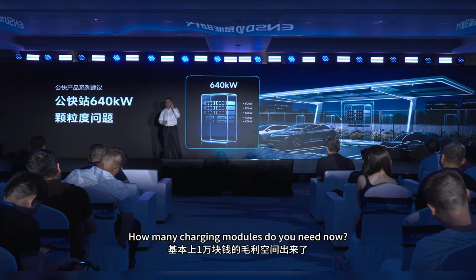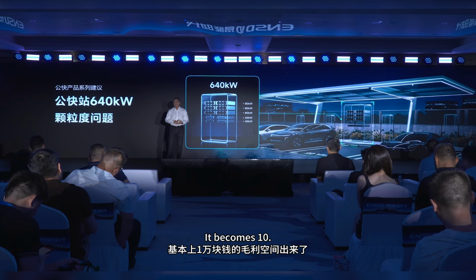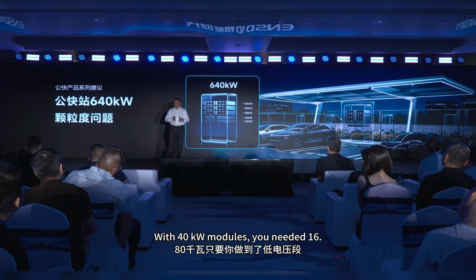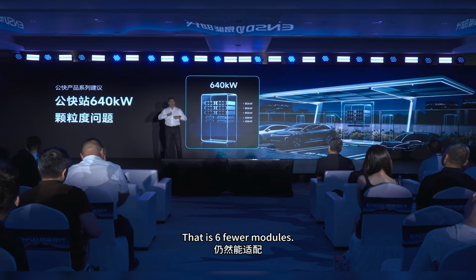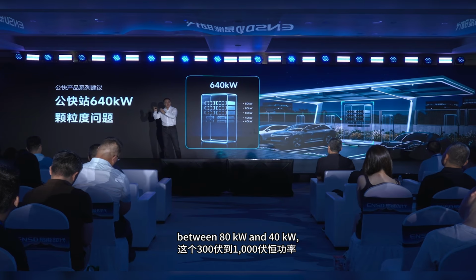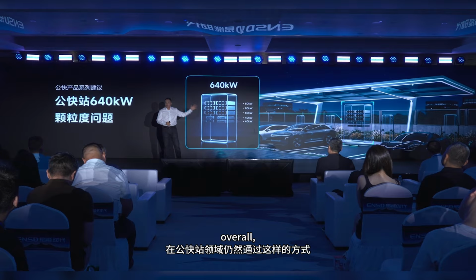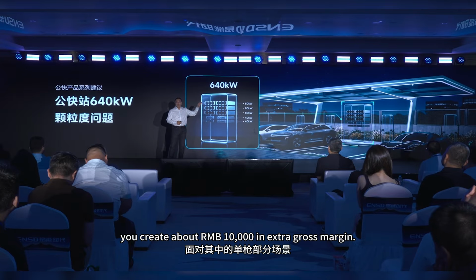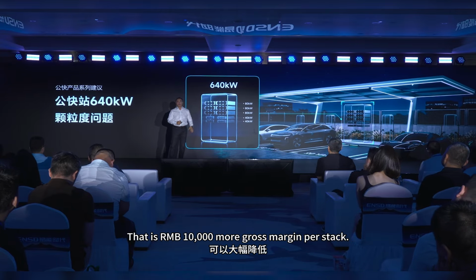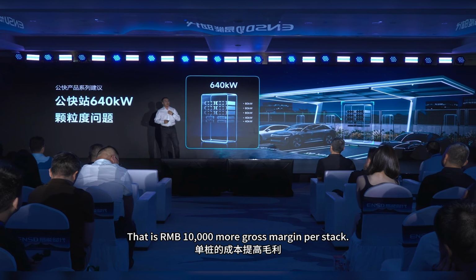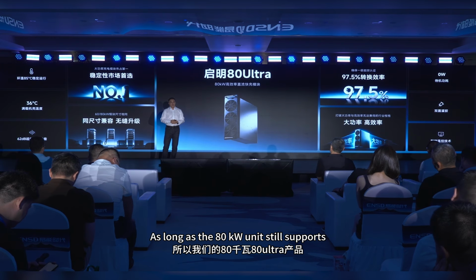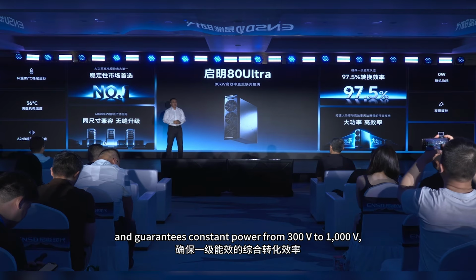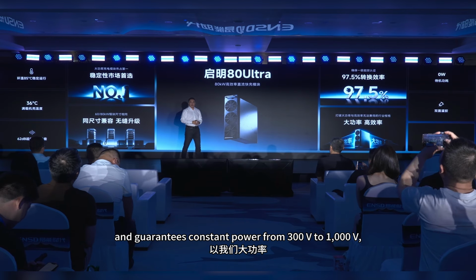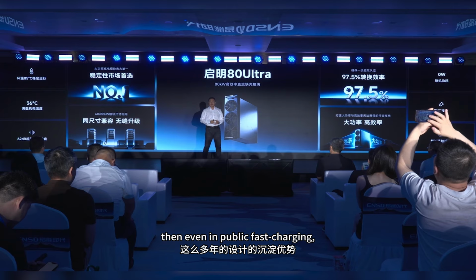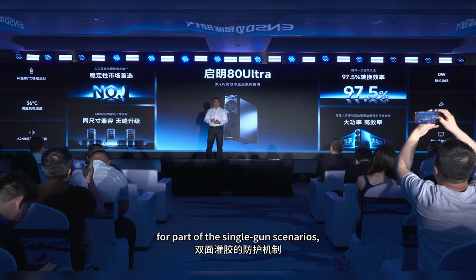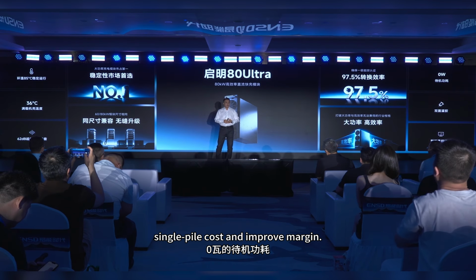But think about it. How many charging modules do you need now? It becomes 10. With 40 kilowatts modules, you needed 16. That is 6 fewer modules, even after considering the cost per watt gap between 80 kilowatts and 40 kilowatts. Overall, you create about RMB 10,000 more gross margin per stack, as long as the 80 kilowatts unit still supports the low voltage range and guarantees constant power from 300 volts to 1000 V. If that is secured, then even in public fast charging, for part of the single gun scenarios, you can significantly cut single pile costs and improve margin.